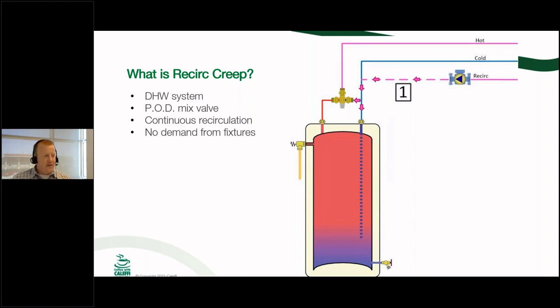Again, the mixing valve, if it doesn't have the ability to completely close off, it's going to add more heat than what it's giving off, and you're going to have some problems. Now, you might be thinking to yourself, Cody, I've got a very simple solution to this. Okay. It's an aquastat. Okay, perfect. I can fix this problem. Okay, I can spend $20 on this aquastat, and I'm never going to run into recirc creep again.